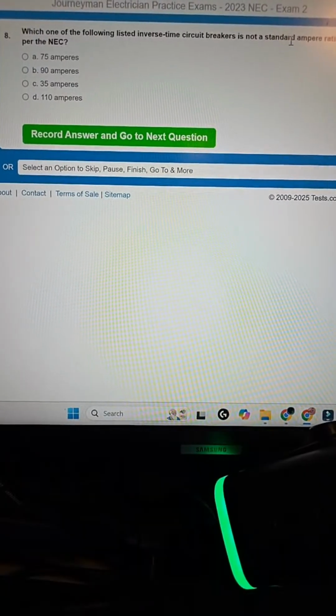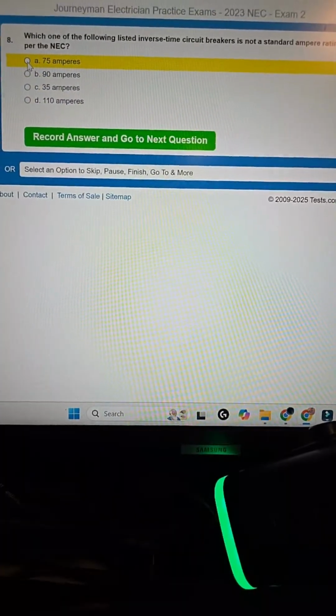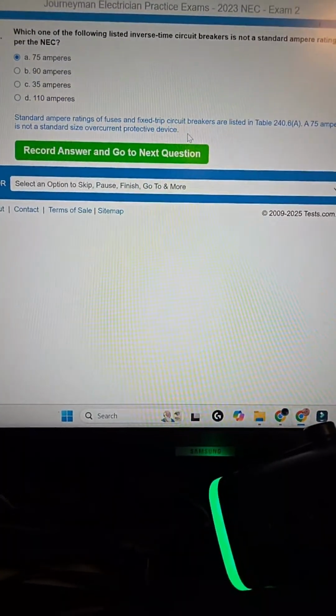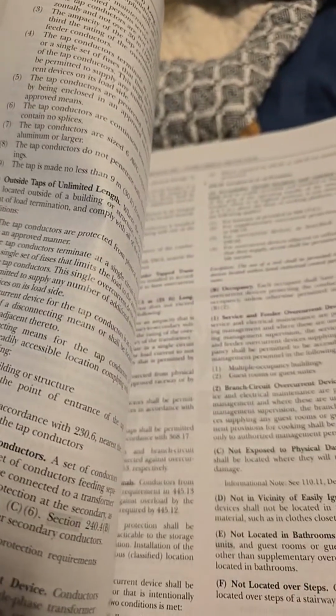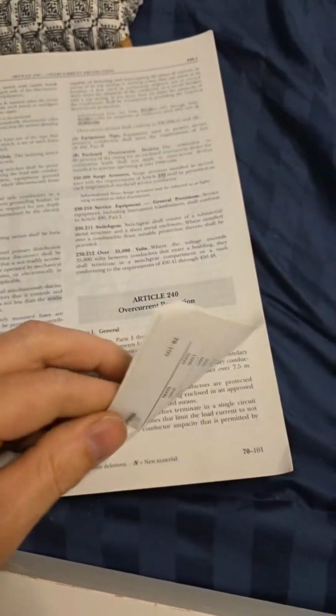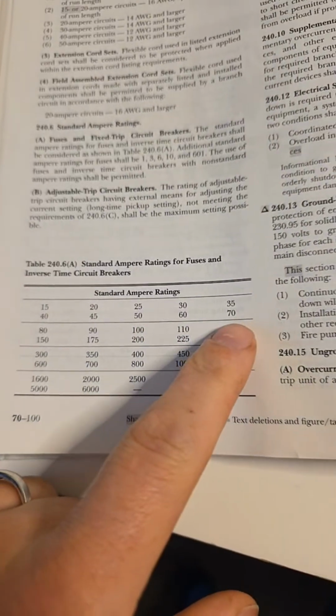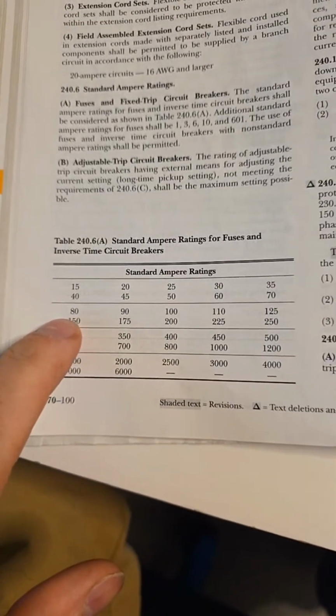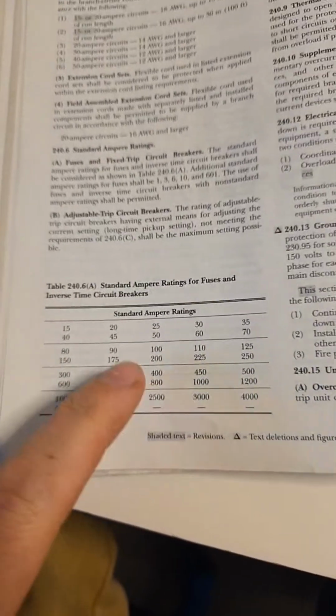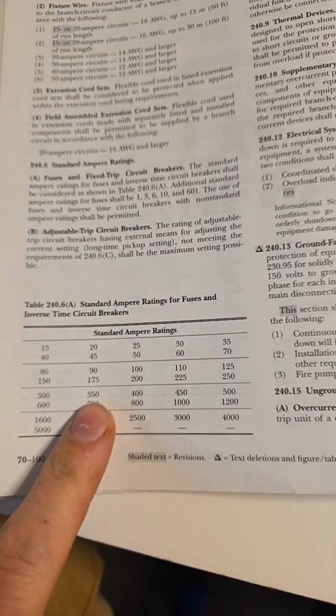One of the following listed inverse time circuit breakers is not the standard ampere rating per the NEC. I think it's a 75 amp, but we can go to 240.6 to find it. So if we go to 240.6 here, because 240 is overcurrent protection, and the .6 is a really, really common page that you'll turn to find the standard ampere ratings here. See, 70 and then 80. So 75 is definitely not a standard ampere rating for fuses or breakers.